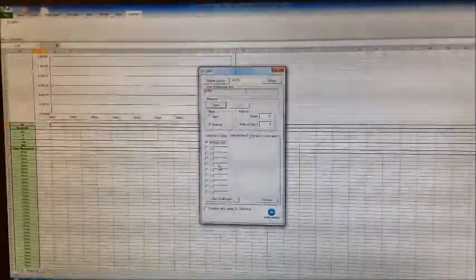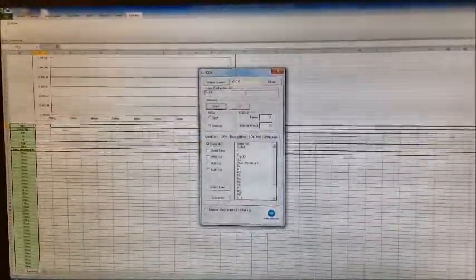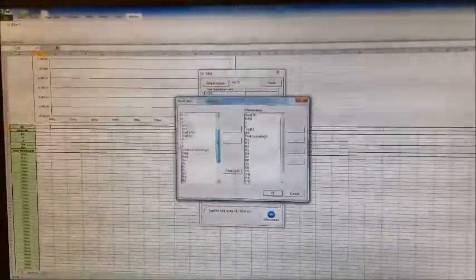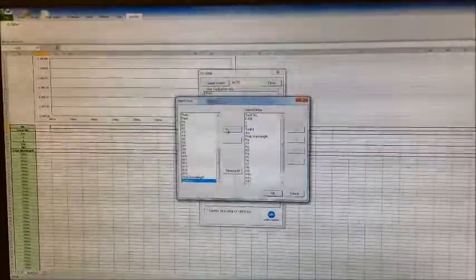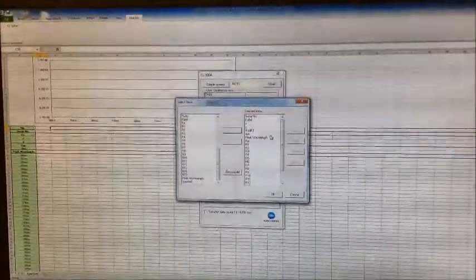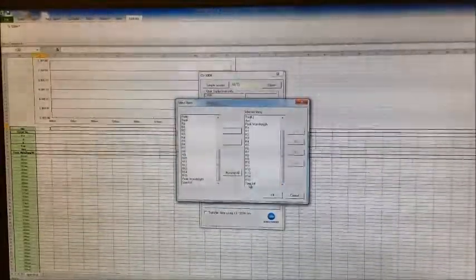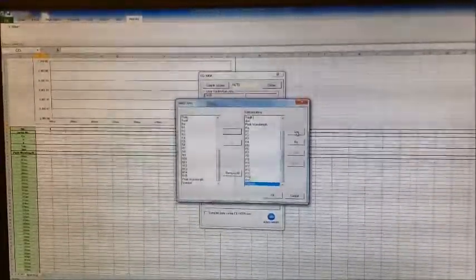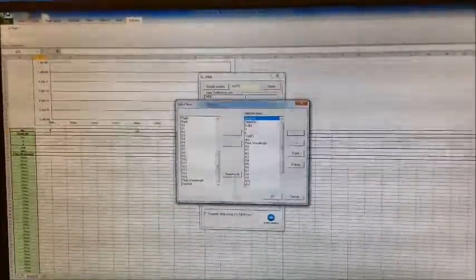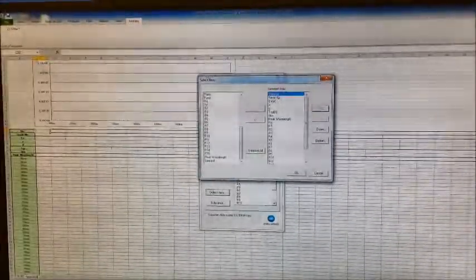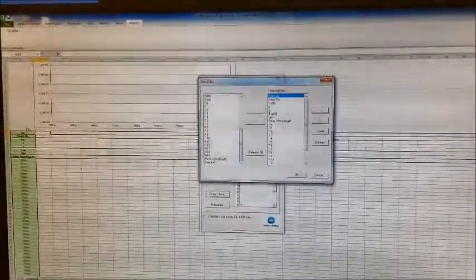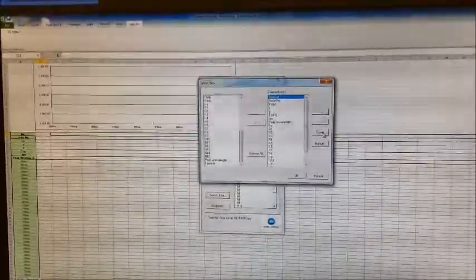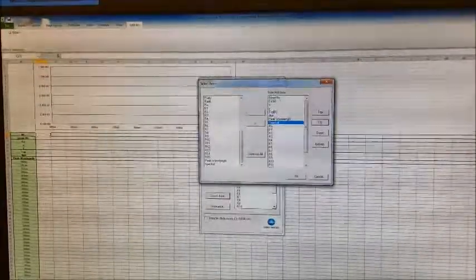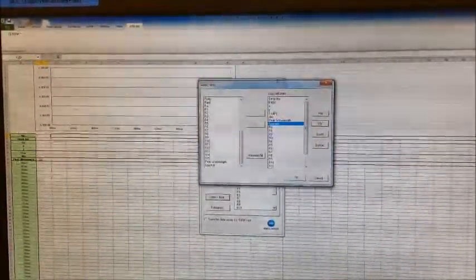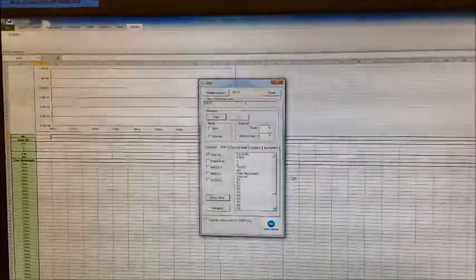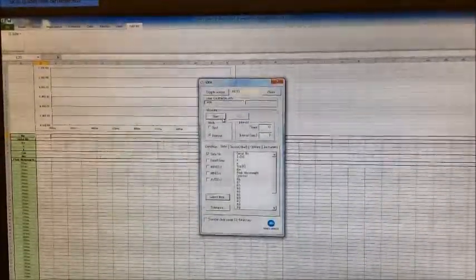Remove it, and we are going to select the data to be measured here. We click on select item, and then we choose spectral to be measured, and we click here to put it on the selected item list. You can see the spectral is on the bottom part of the selected item. We move it to the top by clicking here, and then we should compare that all the selected items are written here in the Excel sheet. So we move accordingly the spectral below the peak wavelength, so that it matches the Excel sheet. Then we click OK to agree with the selected item, and then now we can start measuring by clicking start.